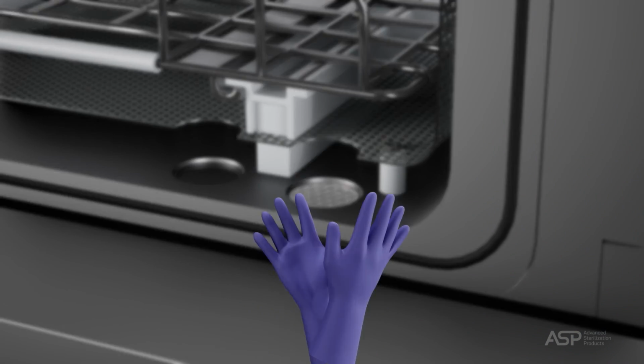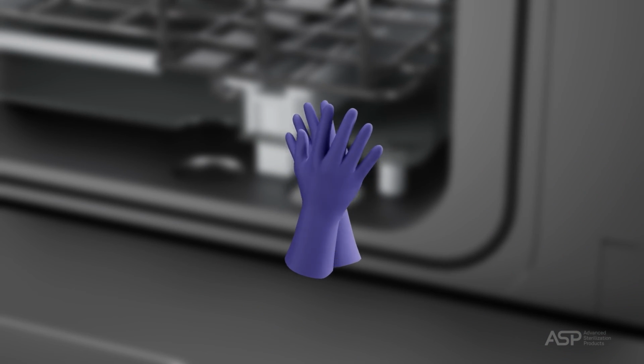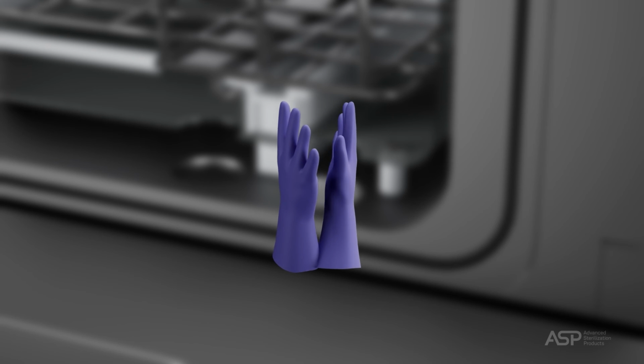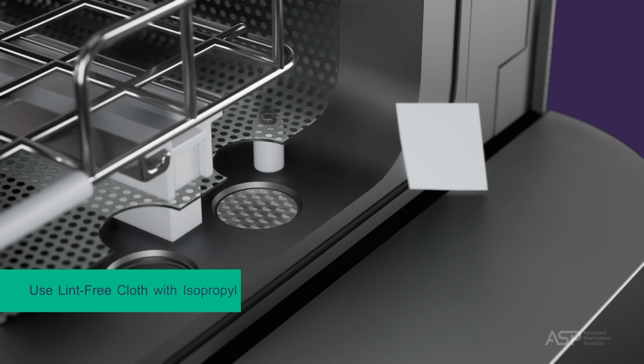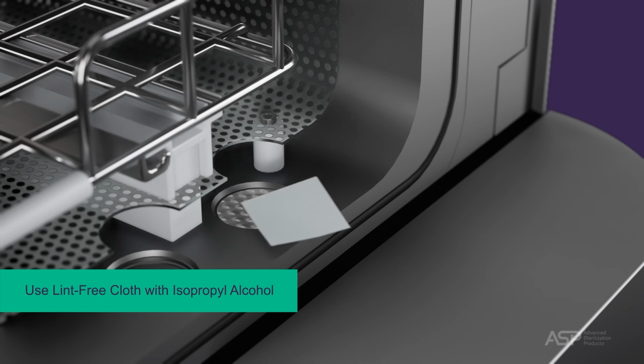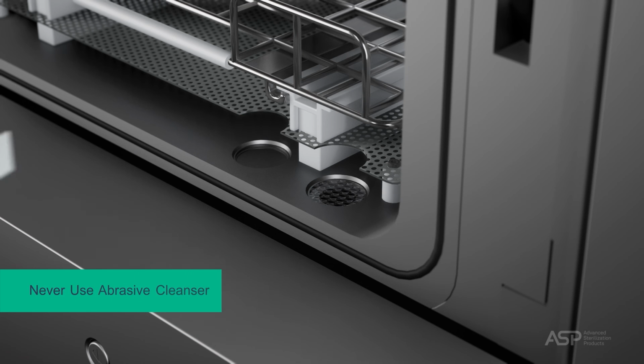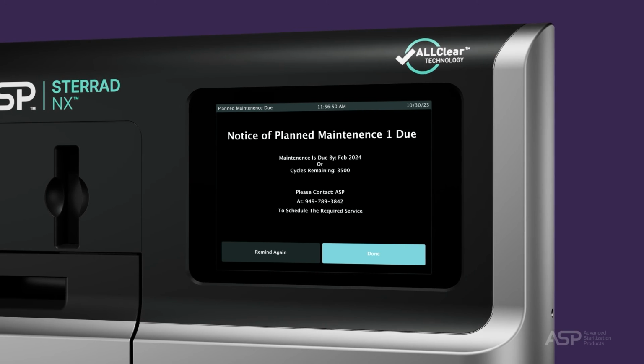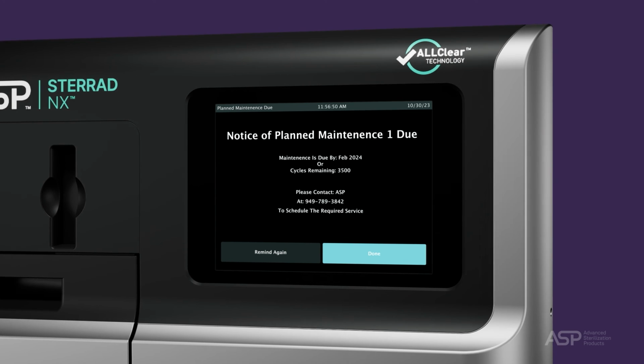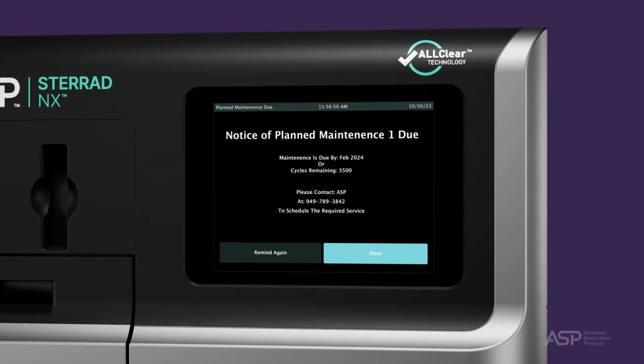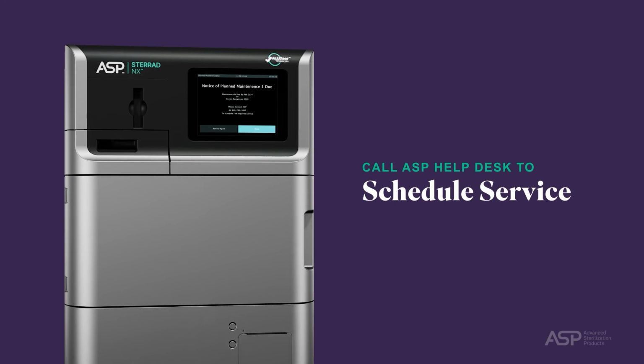To clean the lens, first put on chemical-resistant latex, PVC vinyl, or nitrile gloves. Then, moisten a lint-free cloth with isopropyl alcohol and wipe the lens to remove any accumulated debris. Never use an abrasive cleanser. Regularly scheduled or planned maintenance must be performed at the interval specified on the system. Call the ASP help desk in a timely manner.